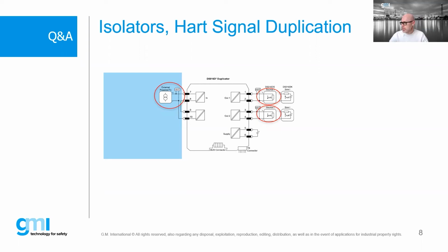Yes, we have two questions from our attendees. The first one is, are SIL-rated HART multiplexers needed in a safety function? Well, in my opinion, all the elements that make up a functional safety loop must be SIL classified. So in case you insert a HART multiplexer in your loop, in my opinion, the HART multiplexer must be SIL certified. Yes, and also, SIL certification is granting that the unit is not interfering with the safety loops.